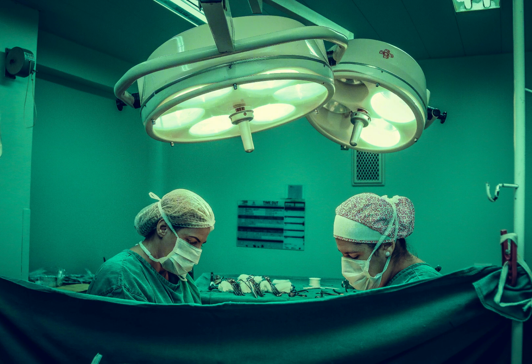Solution number 4. Documentation and tracking. Failed instruments should be logged into tracking systems, so trends can be identified. If a particular instrument or vendor produces repeated insulation failures, that information should be shared with purchasing and clinical engineering departments.